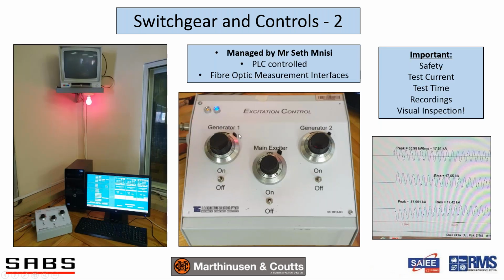Okay, the second part, the switchgear and controls, they're managed by Seth. He's an organizer here this afternoon, so you can ask him whatever you like. They're PLC. So although the equipment's old, it's PLC controlled, and the measurement interfaces are fiber optically isolated, so extremely safe. I love this red light in the corner of the room. That's what you want to see. The red light means the plant is operating, and much of your control is done here.